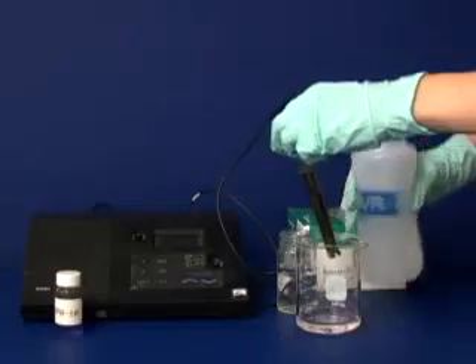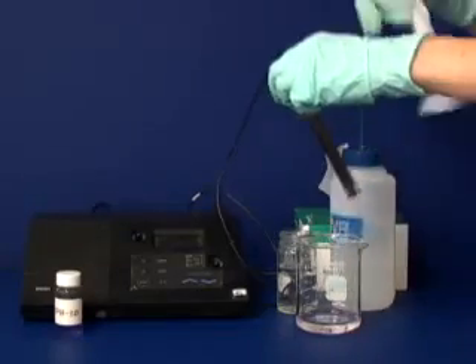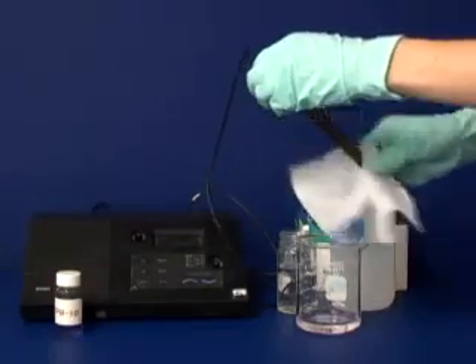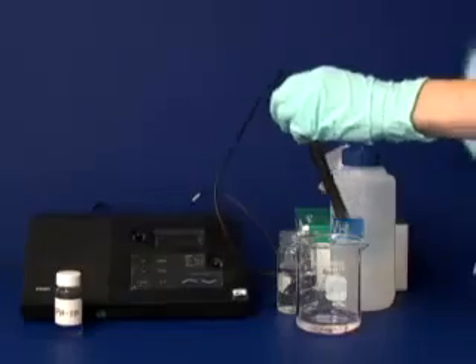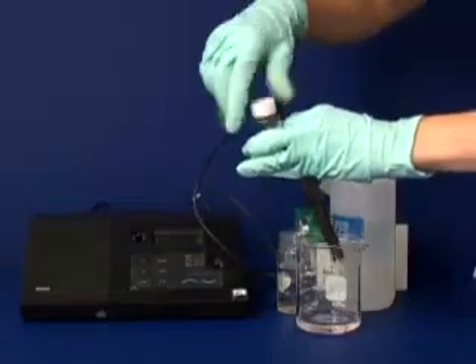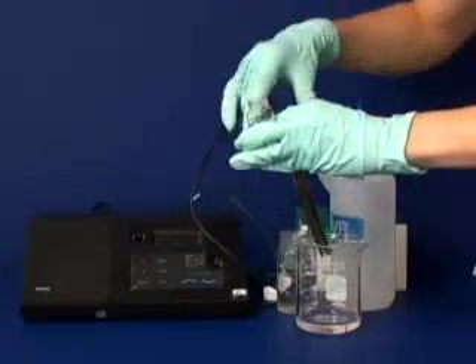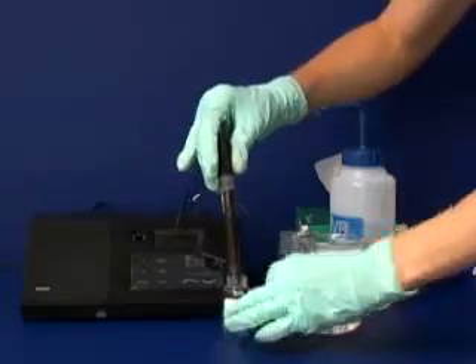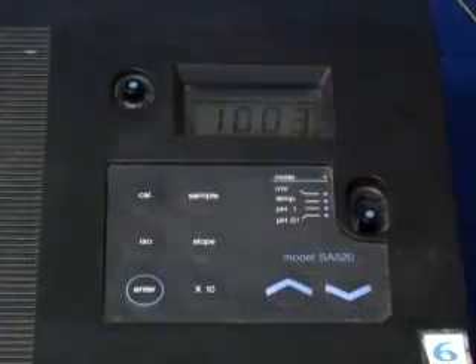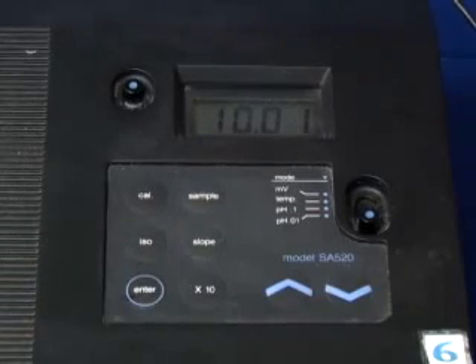Rinse the probe with distilled water, blot it with a Kim wipe, and place it into the second buffer. If your solution has an acidic pH, then use the 4.01 buffer. If it has a basic pH, use the 10.01 buffer. The display will alternate between 2 and the pH value of the solution. Wait until the display stabilizes and press Enter. The letters pH will be displayed, indicating that the pH meter is now ready to take measurements.